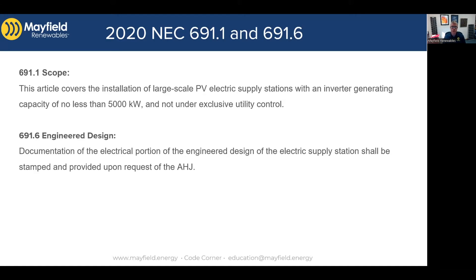The scope also addresses not being under the exclusive control of the utility. It's important to know what generating capacity is — it's actually the AC output of the inverters, the sum of the inverters' AC power output, the continuous power output at 40 degrees C. So for large scale systems, the 5000 kilowatt threshold is an AC value and it's a very specific value of the inverter output. That definition also shows up back in Article 690.